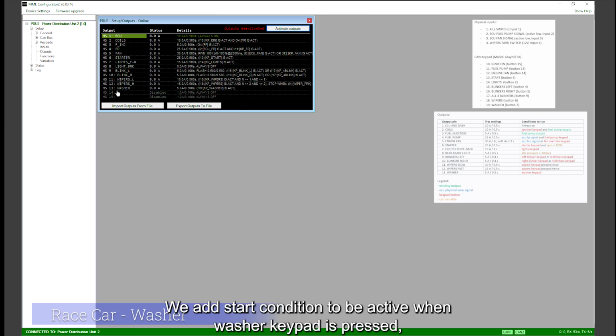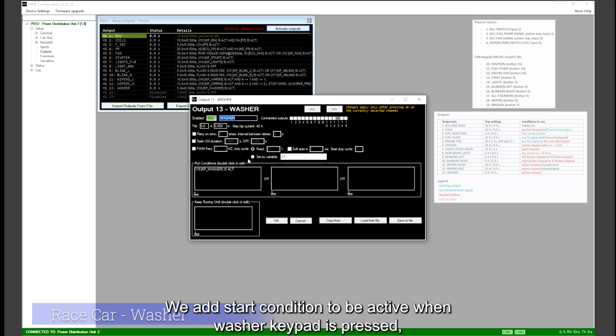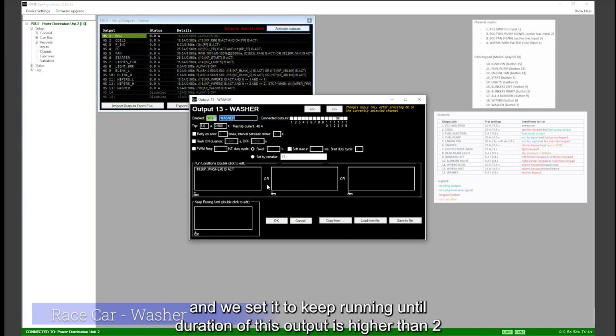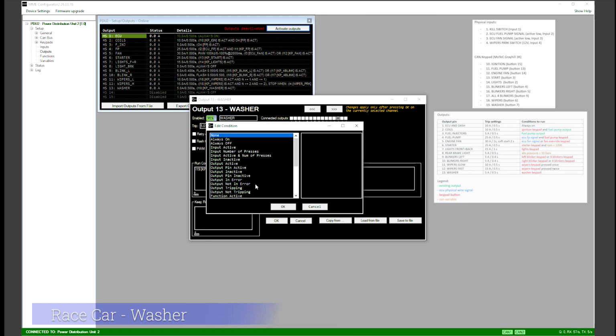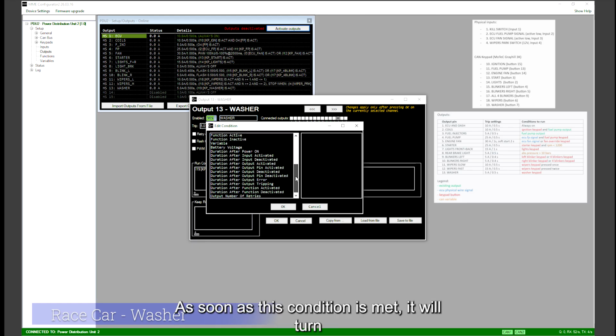We add a start condition to be active when the washer keypad is pressed, and we set it to keep running until the duration of this output is higher than 2 seconds. As soon as this condition is met, it will turn off.